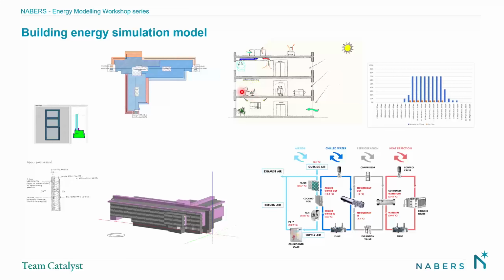Okay. Equipment loads, computer loads, fax machine loads, whatever else is in your office building or other building which is producing heat, provide sensible loads to the buildings. And within the NCC, there are limits to how much you're allowed to use. So for lighting, for equipment, and for people, these things are specified depending on the type of building you are using. Okay. Now, the last thing to think about is how air exchange happens in a building. The air brings with it heat and moisture, or takes away heat and moisture, depending on what you're doing. So we have what we call ventilation load.